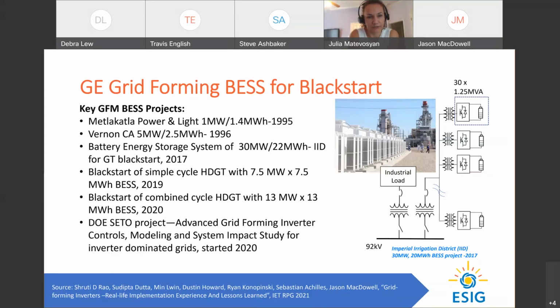The rest of the projects on the list are used for black start, where battery storage is used to black start heavy duty gas turbines. Initially those were started up by diesel, and the gas turbine effectively became the black start unit for the rest of the grid. But because of environmental and emissions constraints these gas turbines faced, they looked for alternatives instead of diesel, and that's where grid forming batteries were implemented. The grid forming battery initially starts up these gas turbines, and then the gas turbines effectively become black start units that can participate in black starting parts of the grid.